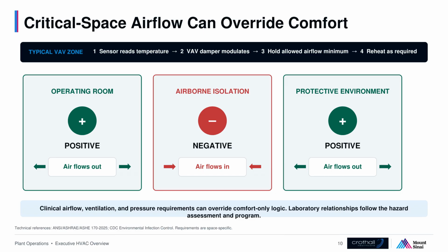The direction of airflow matters. Operating rooms are typically maintained positive to adjacent areas, so air flows out. Airborne infection isolation rooms are negative, so air flows into the room and contaminants are contained. Protective environment rooms are positive to help protect highly susceptible patients. Laboratory relationships depend on the specific hazard assessment and program. There is no single temperature, humidity, air change, or pressure value for every hospital space. The adopted code, ASHRAE Standard 170 edition, approved design, and clinical use determine the requirement.